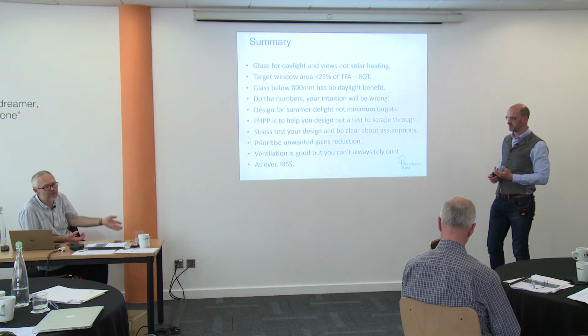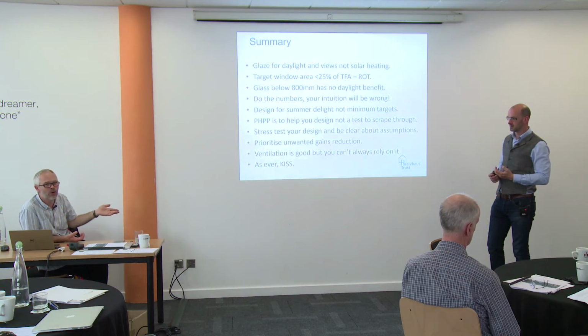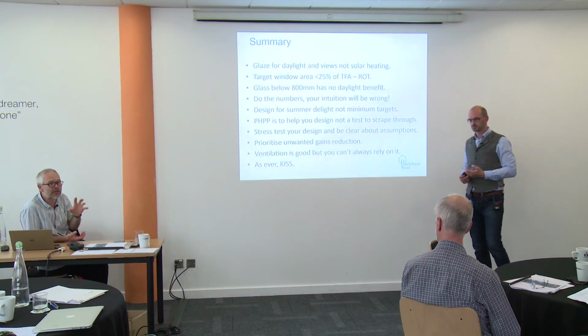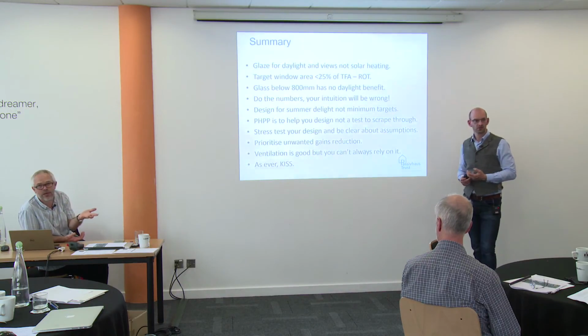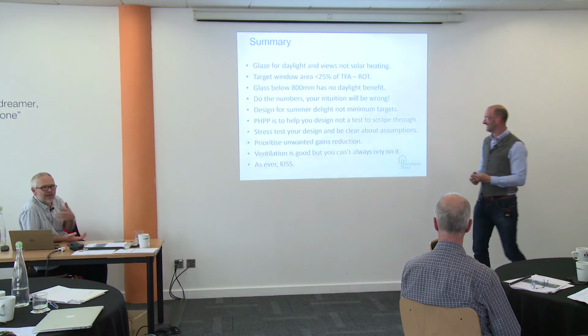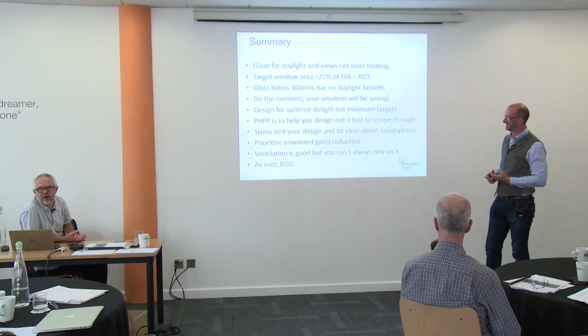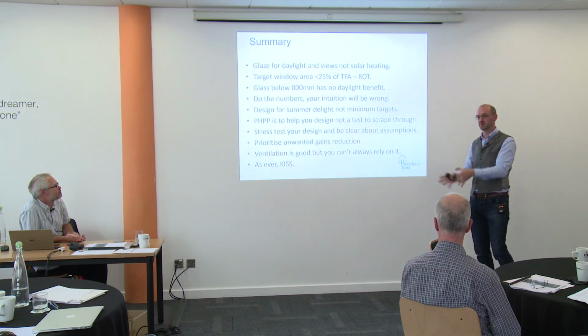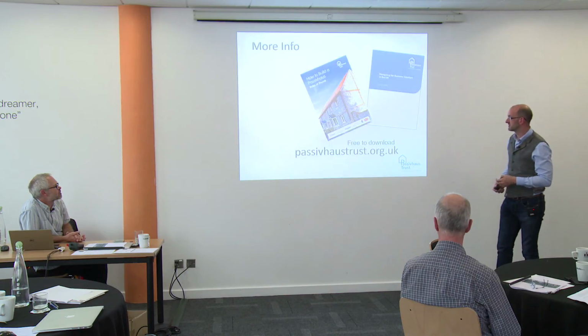So now we just say, look, just leave it running, open the windows, summer, winter, do what you want. If you want the windows open, open them, shut them, don't care. But the MVHR keeps going and you just forget about it. You're not having to think, is it winter or is it summer? How do you decide when it's summer in this country? It's really hard. Suddenly it's winter again and then it's summer, you can't program it. So it's got simpler really, some of this stuff and some of the earlier ideas, and it's using very little energy. Basically, just try and keep it as simple as possible. The world can be a lot more complicated, but you keep your design and your design processes simple and straightforward. More info in the rules of thumb.